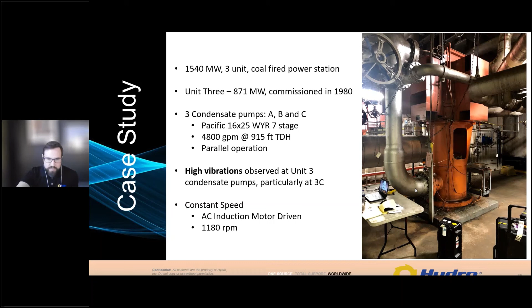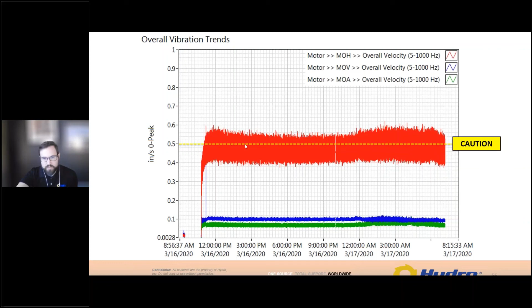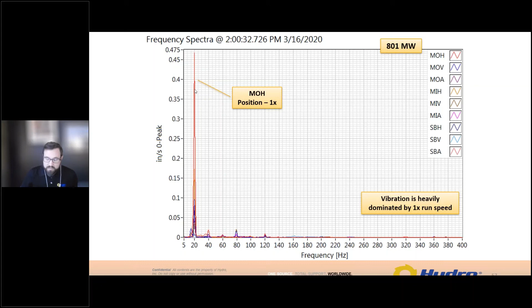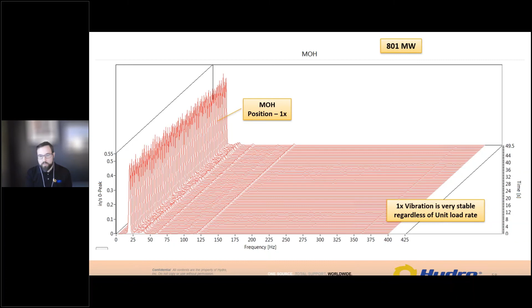We did some observations on this pump. We saw a highly directional vibration. Okay, so already it's very suspicious. Most of that vibration energy is in the 1x, so we see a very high peak in the 1x. This is a recently repaired machine though, so this is not something that has a big imbalance, and I can go back and look at the history of that. I also see that this is very stable across the load rate of the plant. So it's a constant speed machine, but it varies in flow rate as the plant ramps up to maximum megawatts. And I see that really prominent 1x stays there regardless of the load rate.